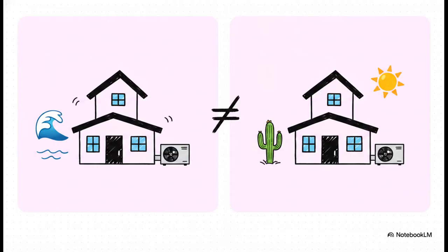This comparison perfectly illustrates why that lazy rule fails so miserably in our area. Under California's Title 24, coastal zones like La Jolla or Carlsbad run about 5 to 10 degrees cooler on a summer afternoon compared to inland spots. So a 2,000 square foot home in Carlsbad usually only needs around 2.5 tons of cooling. But take that exact same 2,000 square foot floor plan and drop it into the fierce afternoon heat of El Cajon, and it might suddenly need up to 3.5 tons. Basically, square footage alone simply does not dictate your cooling needs.